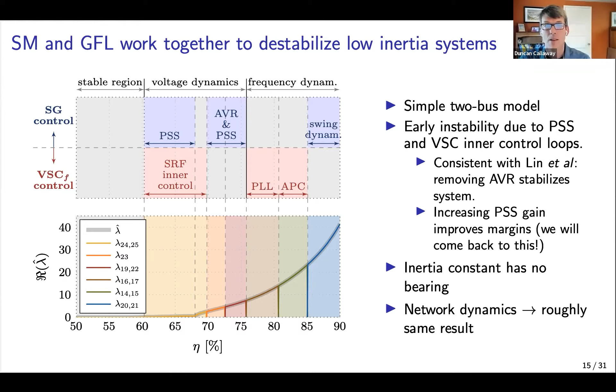A really important point is that the inertia constant has no bearing. So even though we call this a low inertia system, the amount of inertia is not what's causing the instability. It's these other control loops on board the voltage source converter acting with the other control loops on the synchronous generator.